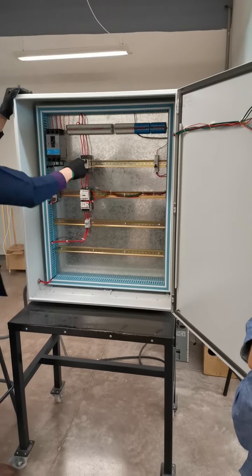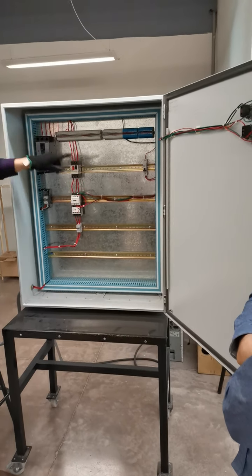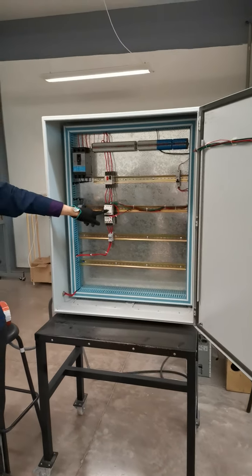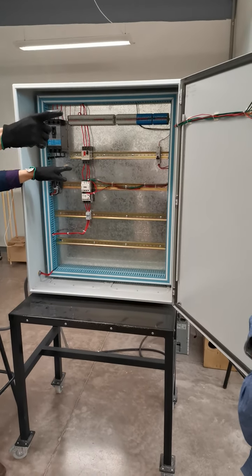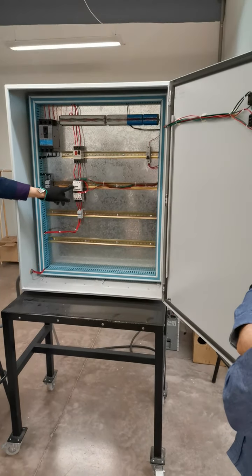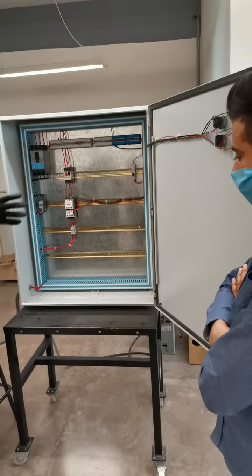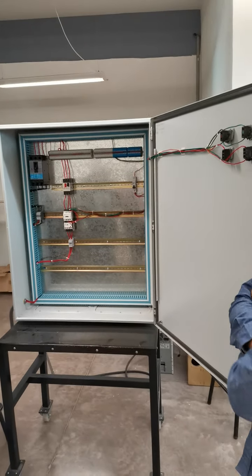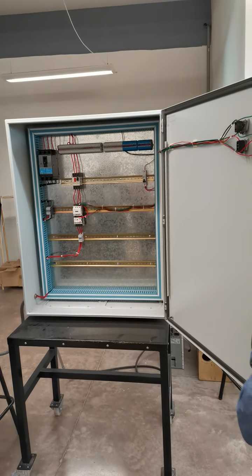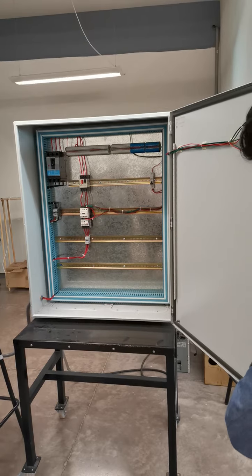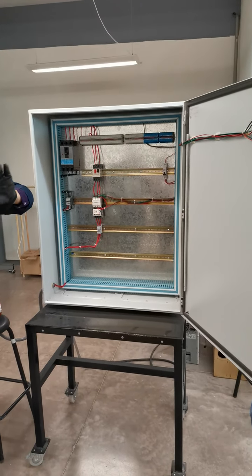You need to press the button in order to activate it. You need to press the button in order to deactivate it. In comparison, the contactor has an electrical activation. You can send an electrical signal, in this case the start button, in order to activate this contactor. And then, for example, this one is already in a latch configuration. With the start-stop, you press the start and the system starts working. If you release the start, the system continues working, and then until you press the stop, the system stops. So this one is already in that configuration.